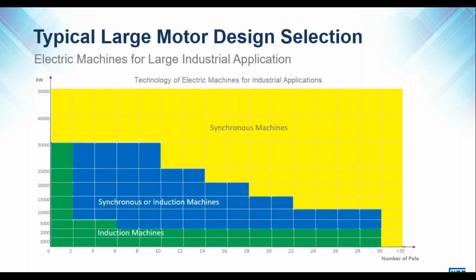And then we have this area in between where we can really choose to use either a synchronous or an induction motor. Both would be capable to operate within this range of applications. The choice here comes down to whether a synchronous machine is needed for a specific purpose. That would be to adjust the power factor for reactive power compensation, or if the process specifically demands or requires a synchronous machine.